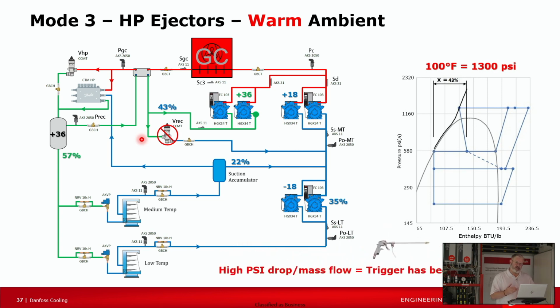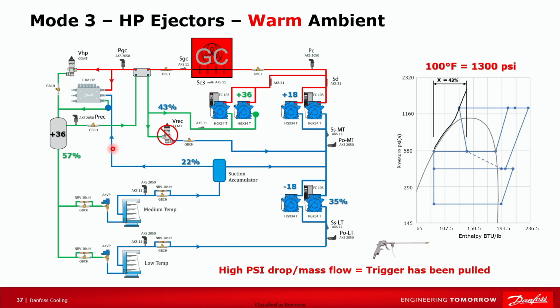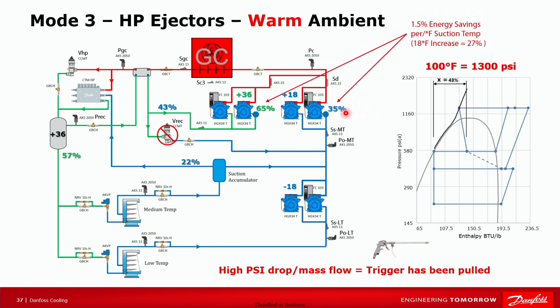If we've pulled the trigger on the wand, meaning we've got high pressure drop across the ejector and we've got high mass flow, we're going to create a condition that makes that 22% go to the left on our diagram, and it's going to slowly weave its way back over to our parallel compressors. And the magic of the ejector block is this. At this point, we're now running 65% of our overall system mass flow on a plus 36 compressor. And that includes serving the plus 20 medium temp evaporators. And that only leaves 35% coming to our medium temp compressors, because all it's doing now is servicing the low temp load and compressors.